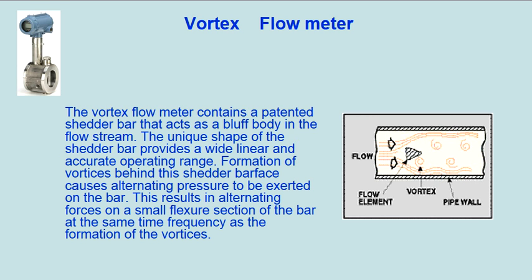The Vortex Flow Meter contains a patented shedder bar that acts as a bluff body in the flow stream. The unique shape of the shedder bar provides a wide linear and accurate operating range. Formation of vortices behind this shedder bar causes alternating pressure to be exerted on the bar, resulting in alternating forces on a small flexure section of the bar at the same frequency as the formation of the vortices.